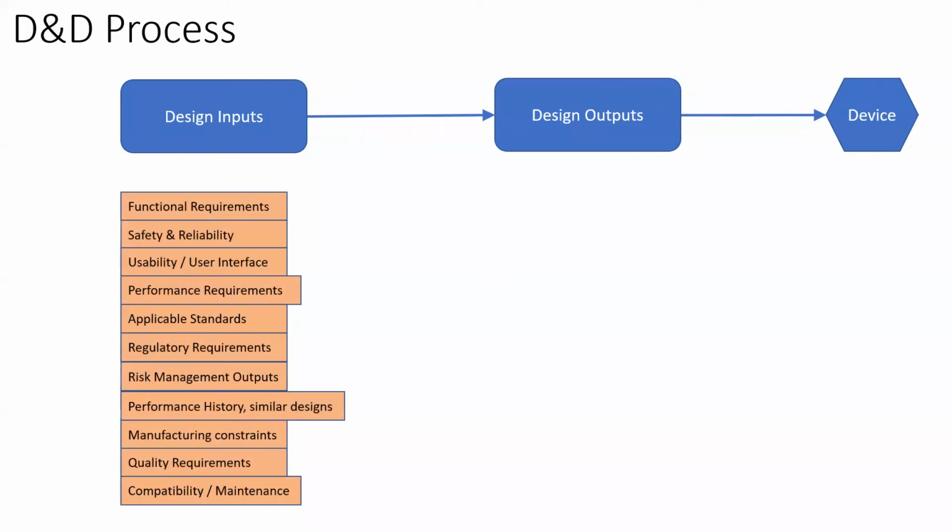So every requirement that a device eventually needs to fulfill, expressed in clear, quantified engineering terms, is a design input. So it could be a functional requirement, it could be safety requirements coming out of a standard, it could be a reliability requirement in terms of life, it could be a usability requirement in terms of handling, it could be a performance requirement which may be connected to a test standard, it could be an applicable mandatory standard by some organization, it could be a regulatory requirement, it could be a risk management output.